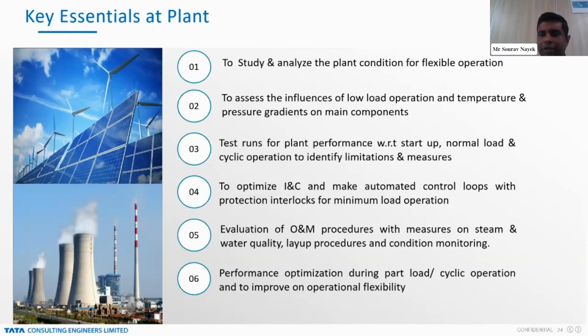With respect to the coal supply, the airflow, the steam pressure, the entire control loops have to be largely automated, and all the protection interlocks have to be there, so that we maintain this minimum load condition and a proper operation of the thermal power plant.